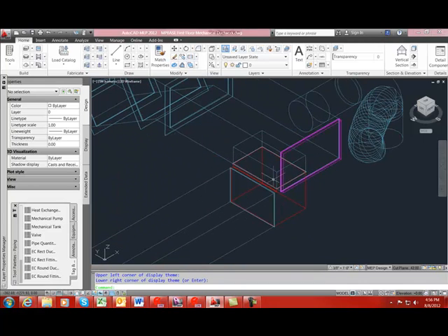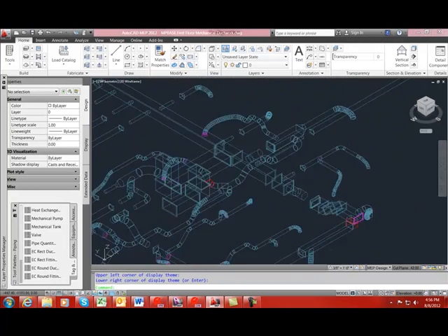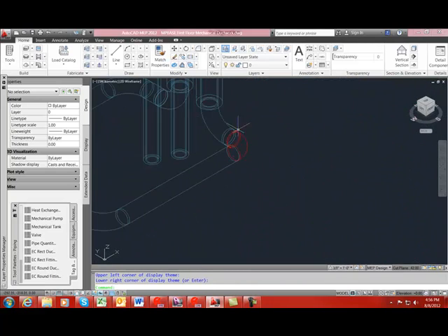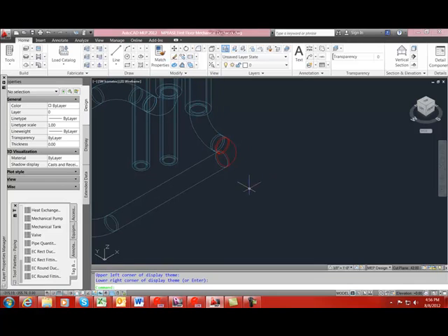Now if we go through our drawing here, we see we have a square elbow that's red, a round gore elbow, and another round gore elbow up here as well. Rather than force the creation of the fitting and potentially moving the center line of the ductwork, we color the items red and let the detailer make decisions on how this area should be fabricated. On this particular import, we have 2 round gore elbow errors and 1 square elbow error.